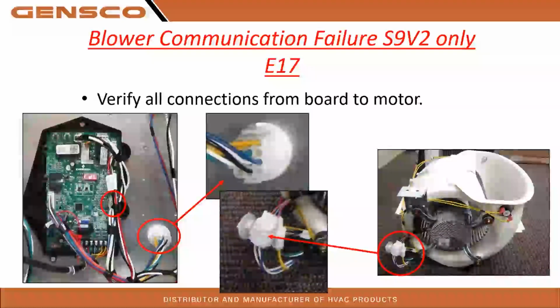So, blower communication failures, S9V2: verify all connections from the board to the motor. There are some connectors there at the gas furnace board. There's a motor connector, which goes into this plug that goes through that essentially firewall, I guess you could say. And it could be plugged straight into the motor, depending on the type of motor, or could have a little whip like this where it plugs in. So you'll want to check that all these connections are good and solid.